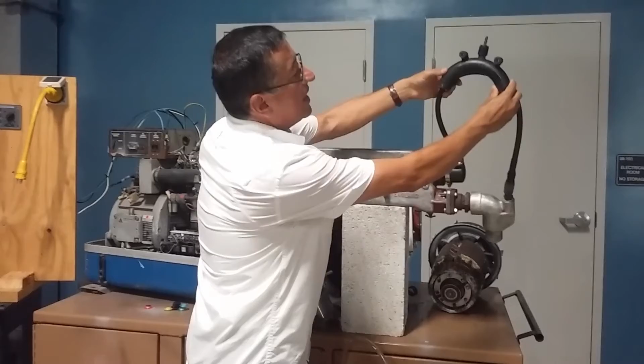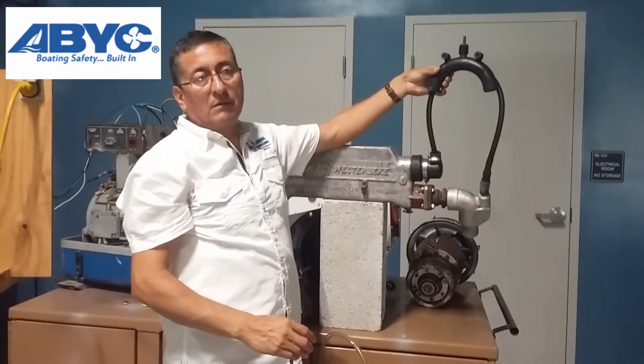What is the separation in between the level of the water line and the vented loop? The separation should be minimum 12 inches. I recommend the maximum that you can. It's better.